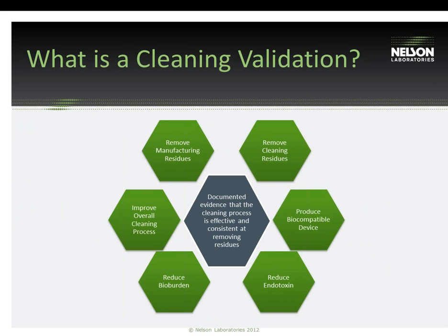So what is a cleaning validation? A cleaning validation is documented evidence that the cleaning process is effective and consistent at removing residues and contaminants from the manufacturing and cleaning process. There are three real important points to note with this definition. The first being that this is documented data. If an auditor were to come to your facility and ask if you were producing and manufacturing clean devices and you say yes, how can you back up that claim? And what data do you have on file to show that auditor?